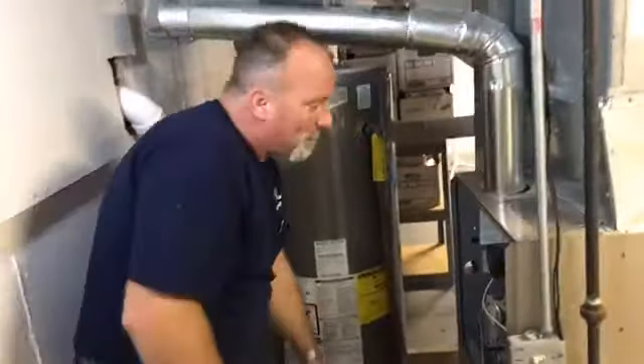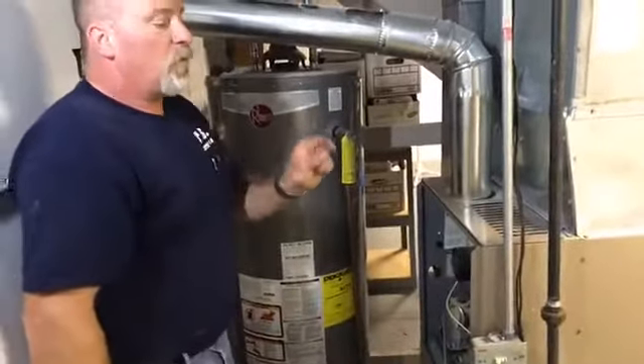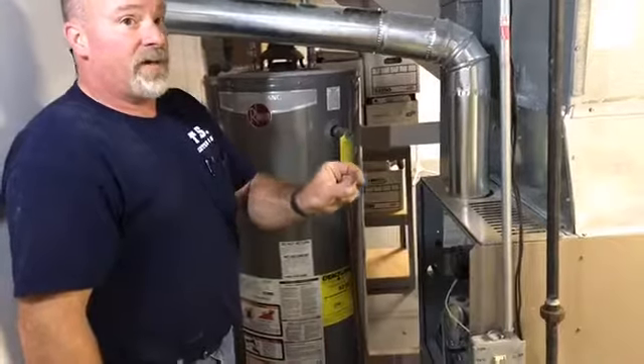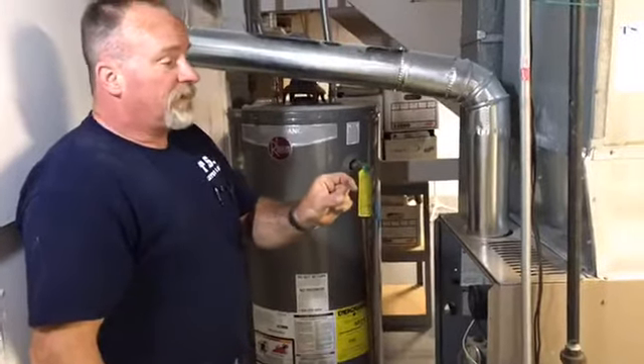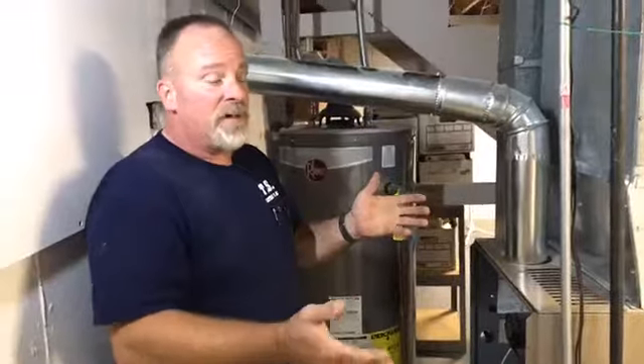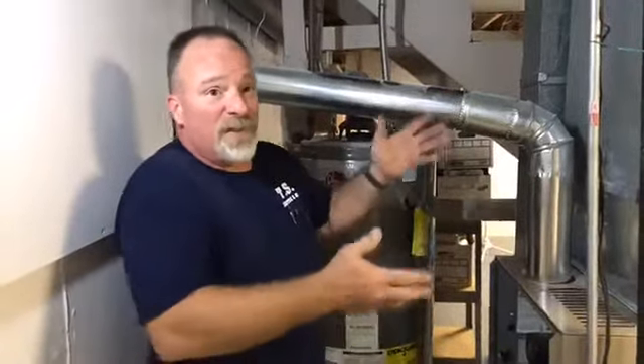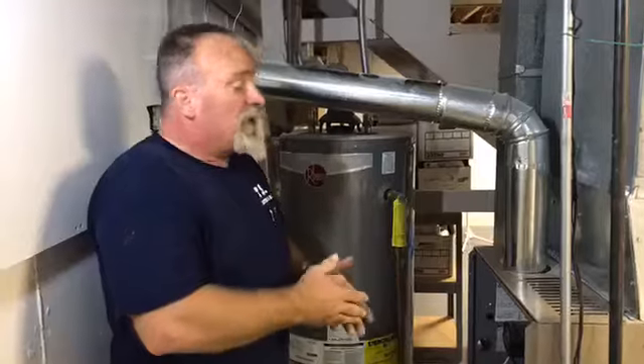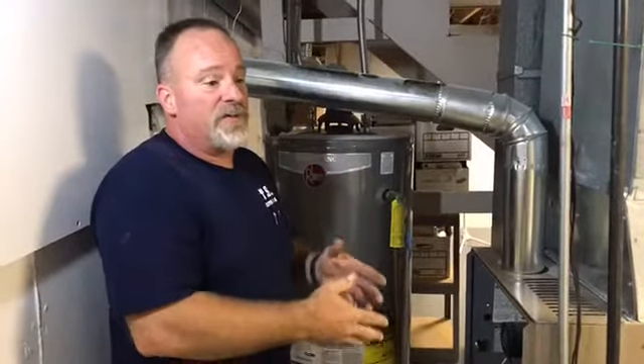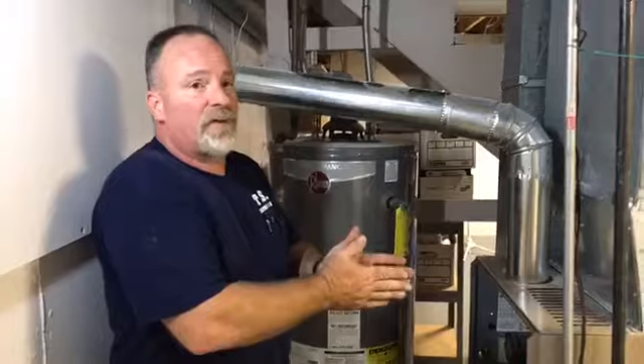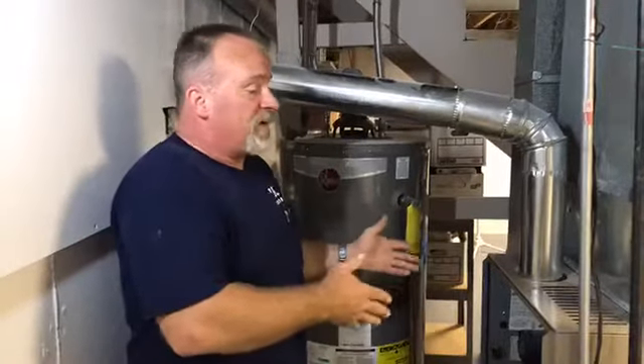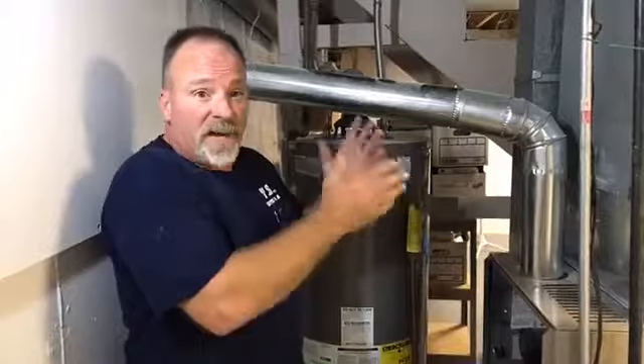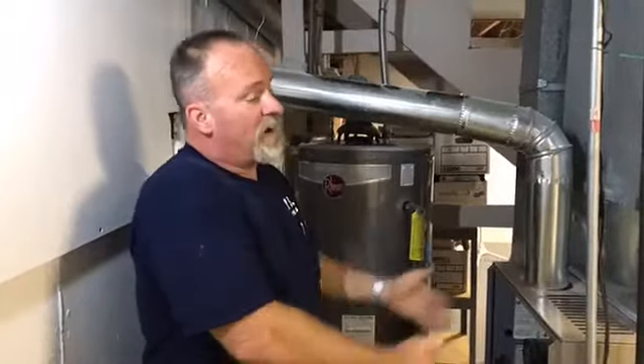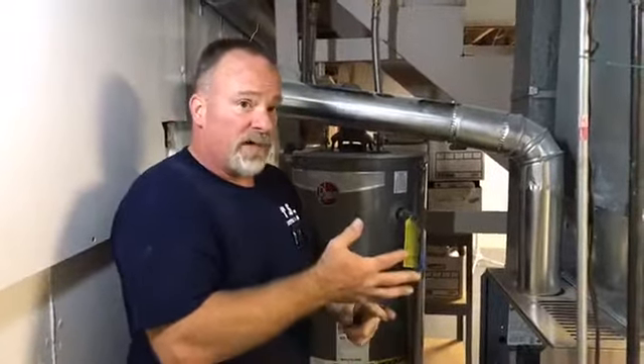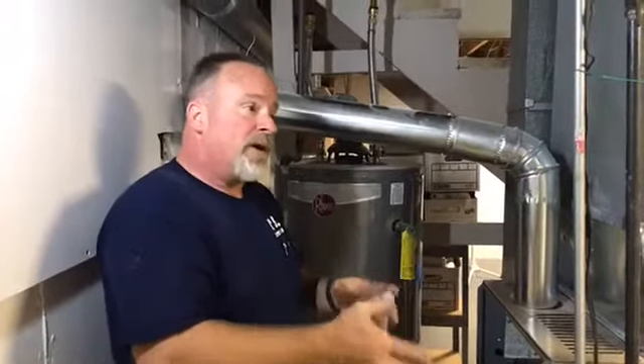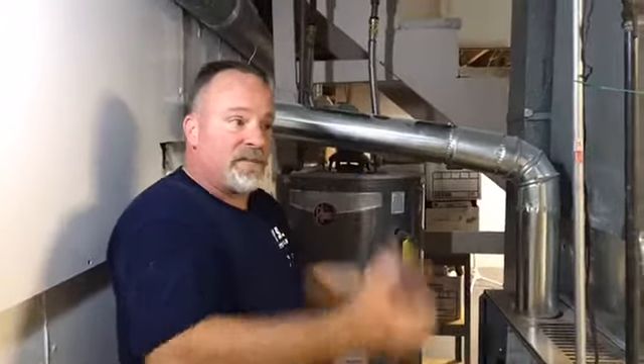And the furnace filters, how often do you want those changed? About every 6 months? Or? 1-inch filter every 30 days. Oh, okay. Even though they say they can last up to 3 months, that's if your furnace isn't running, maybe over the fall and the spring. During operation, those need to be changed every 30 days. Restrictions in the air filter cause more problems, and it costs you money too. Right. This machine's designed to move air. If I can't move that amount of air through the heat exchanger, the heat exchanger overheats, and you're spending more money in fuel to heat the air because we're just not moving as much.